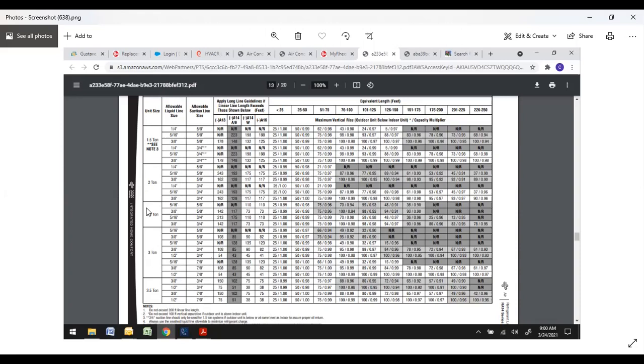So if you have any questions as far as if the line set is correct, in every installation manual, this is in here, and it's also in the specification sheet. So just figure out which tonnage you have, see what line set you have, 3/8, 3/4, and you're good up to about 125 feet with a 3/8, 3/4. You know it's acceptable. You can go further.